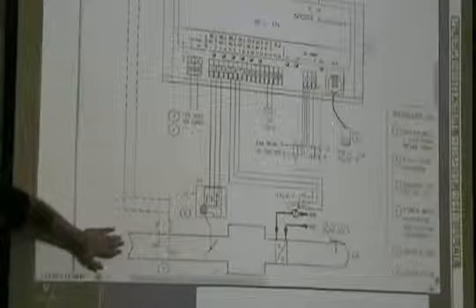If you don't have some type of airflow sensor, is that considered a pressure-dependent box? Mm-hmm. And it'd be a different controller. Okay? This is a pressure-independent controller. And what that means is that the airflow through this box is going to be maintained regardless of the static pressure in this ductwork. Okay? The airflow is independent of the static pressure.